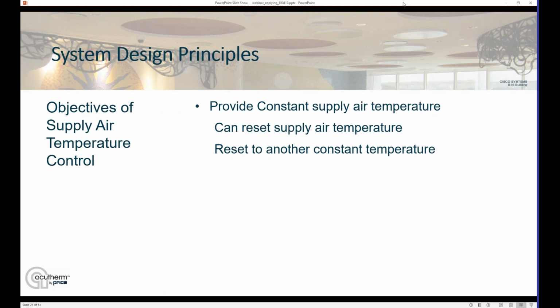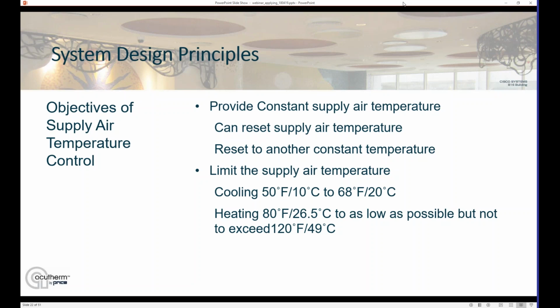And if the supply air temperature is fluctuating too rapidly, the diffuser doesn't know which way to adjust the volume. So a step type function, where a decision is made, a supply air temperature is selected, held for a while, and then later a decision is made to change to another selection, works quite well if you're going to run a supply air temperature reset strategy. Also, we want to limit the supply air temperature. The diffusers use the supply air to determine whether they're in the heating or cooling mode. And for the thermally powered diffusers, these are fixed ranges. So they're in the cooling mode between 50 and 68 degrees, and they're in the heating mode once the supply air is above 80 degrees.